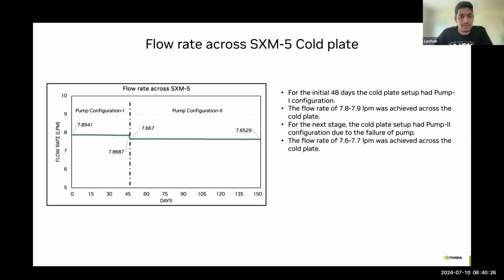This is mostly because of the pump's performance decrease over the period. But from the cold plate point of view, there is no change in the cold plate, and the cold plate was good to operate at higher flow rates or for an even longer period of time.